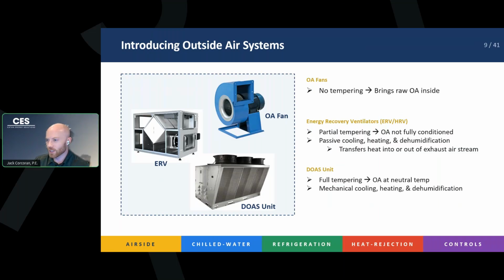Moving down the list, you can use an energy recovery ventilator, or an ERV. Sometimes there's another type of equipment called an HRV, a heat recovery ventilator. Both of these systems pass your exhaust air over the outside air stream. Essentially, if your outside air is at 95 and it's hot, and your space is at 75, but you need to exhaust it, you run your exhaust air past your outside air, and that 75-degree air cools down your 95-degree air slightly before it enters into the space. It's not a perfect system, but it is free.